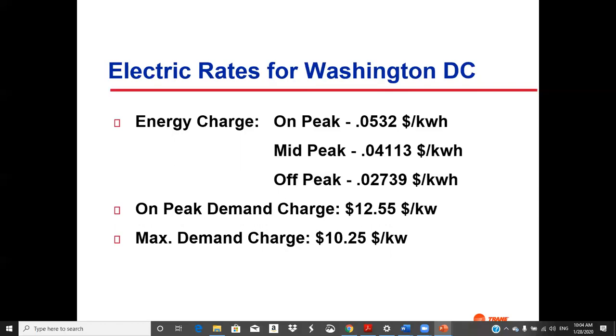There are 2 different pieces of the demand charge, and you're going to pick up both, because if you're running the centrifugal, the maximum demand will occur during the peak period. So basically you get to add these 2 together, and that's $22 and almost $23 a kW. That's a pretty steep demand charge.